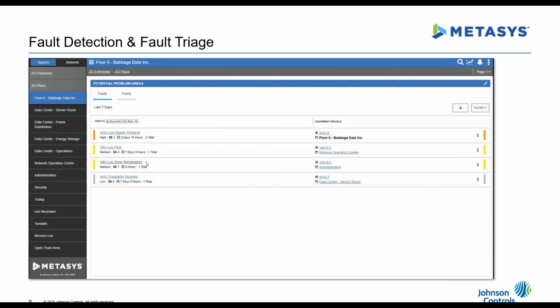We'll have a number of occurrences—on that VAV low zone temperature, we have 7 occurrences—and a total duration, so those 7 occurrences happened over 9 hours. You'll also see something that says '1 total.' We actually roll up all the faults for a particular piece of equipment, this one being VAV 6-2, and if it had more than one fault occurring, similar to the AHU Low Supply Pressure, you'd see two faults.